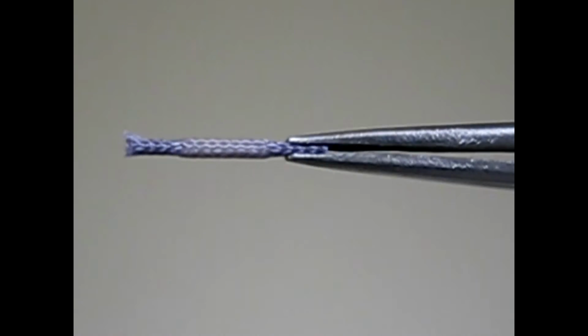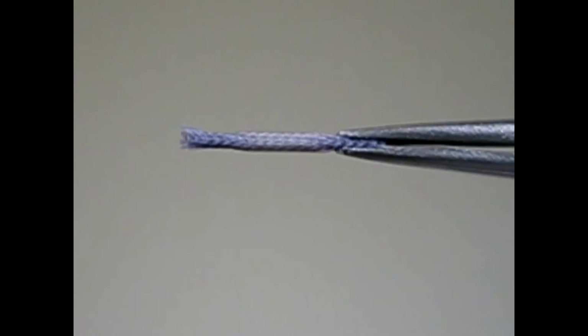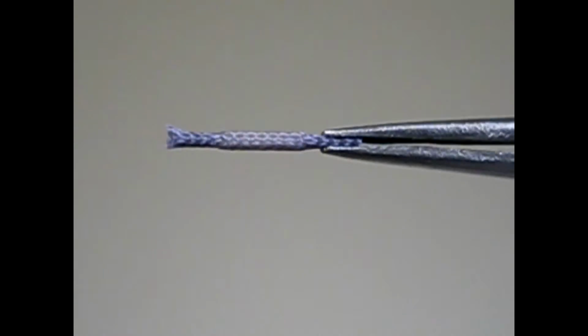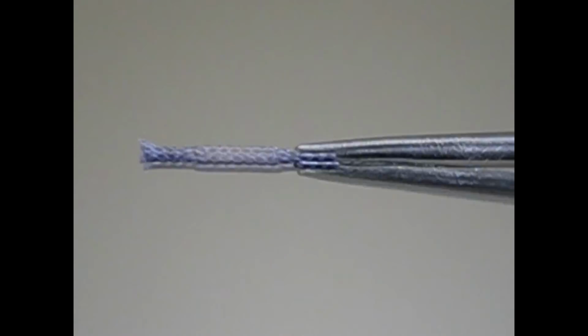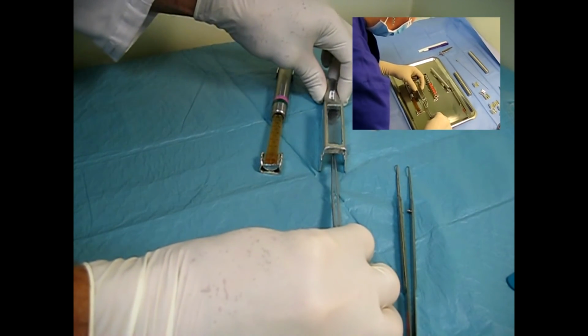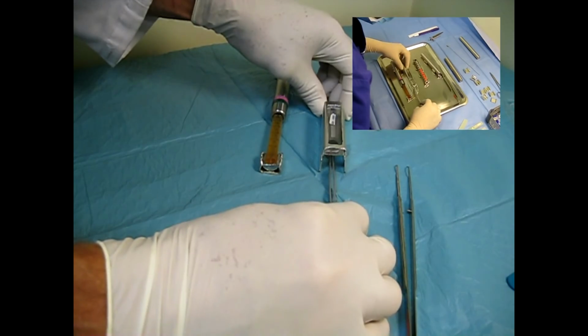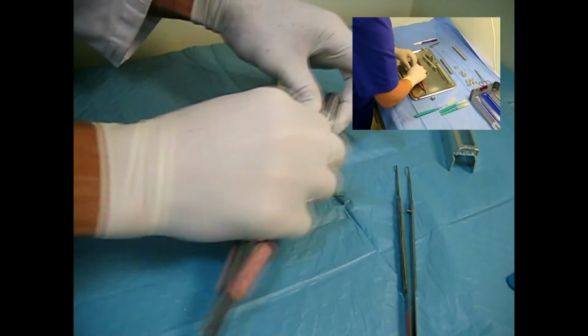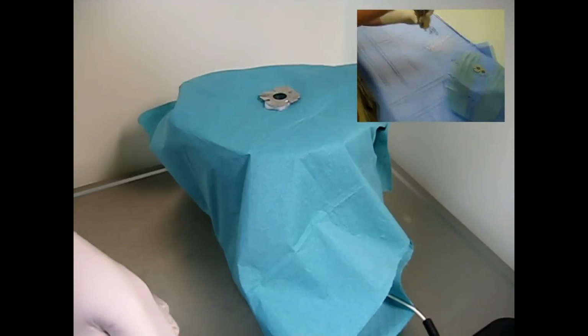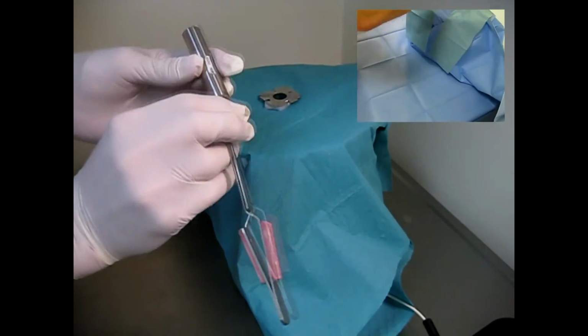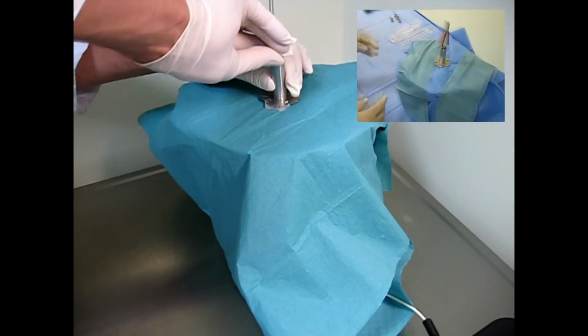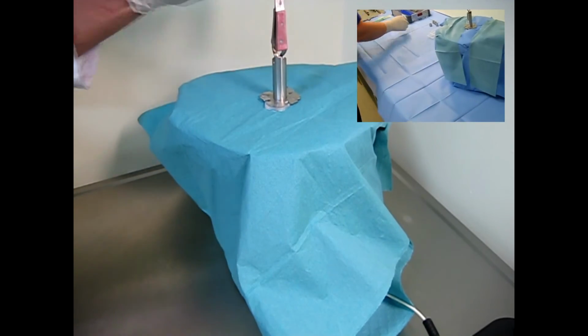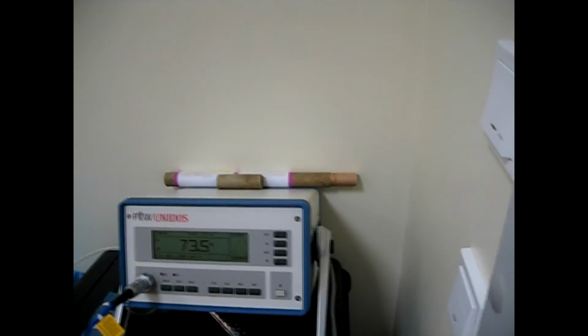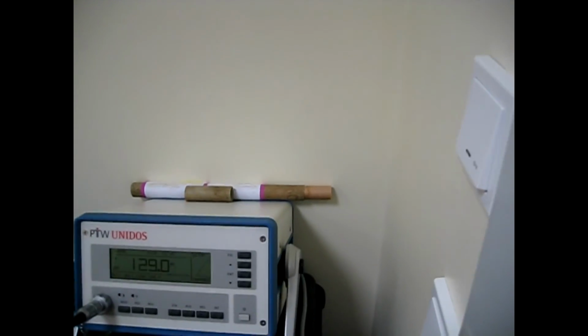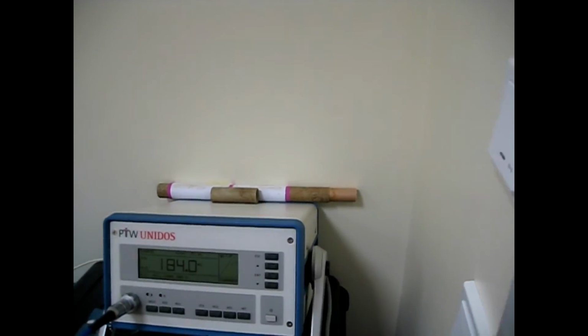Tweezers should hold strands just for its end to avoid shielding of the radioactive part by tweezers jaws. For the transportation strand into well chamber and back, we use short cylindrical container which at the same time play a role a holder for keeping required depth of strand inside well chamber. In this measurement, collecting time of electrometer is 10 seconds.